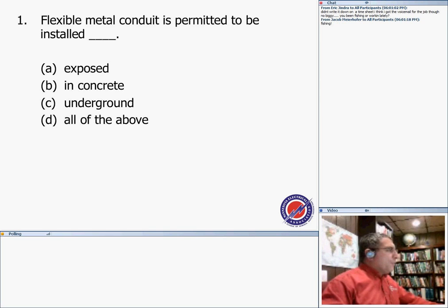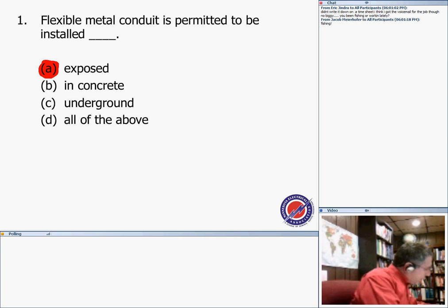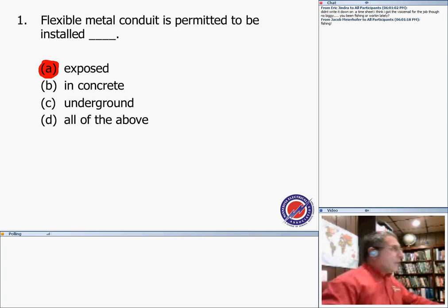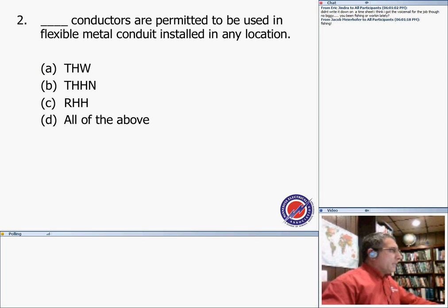Flexible metallic conduit can be used exposed, in concrete if listed, underground if listed. So, well, no, not if listed. This is the most important one, guys. In concrete, yeah, you might have it listed. Underground, for the most part, you don't. So you can argue here, the closest answer is going to be exposed. And I guess anything can be listed, guys, to be underground or in concrete. But based on the rules, which is 348.12, the answer is exposed only, and you can submit anytime.